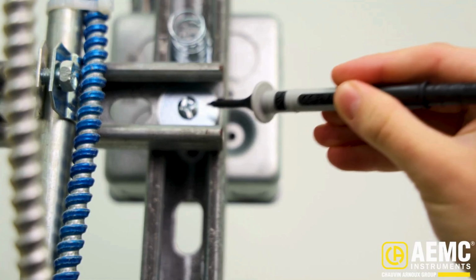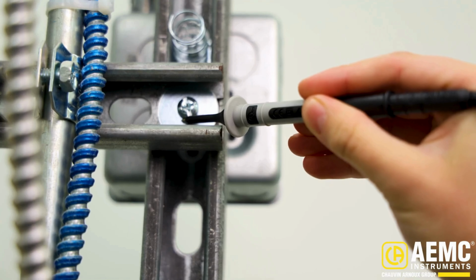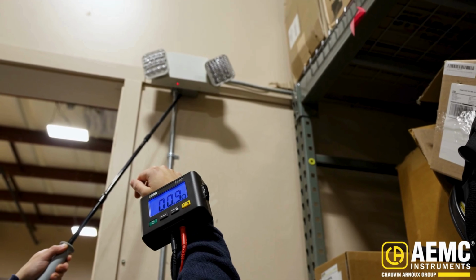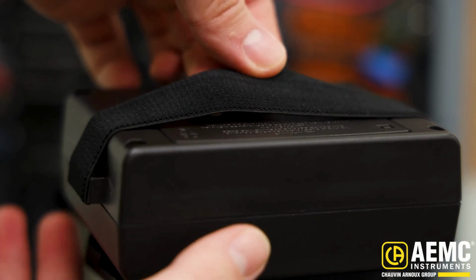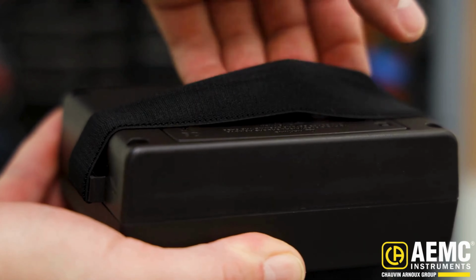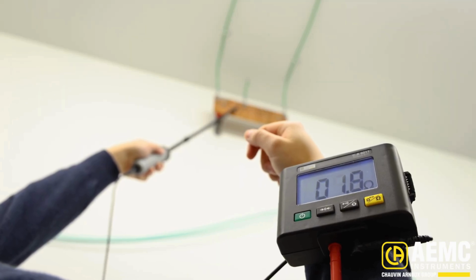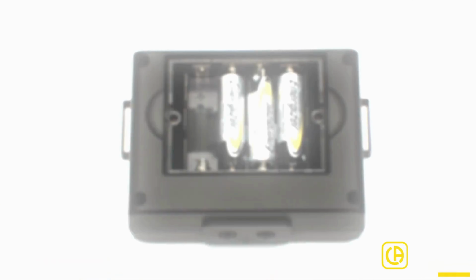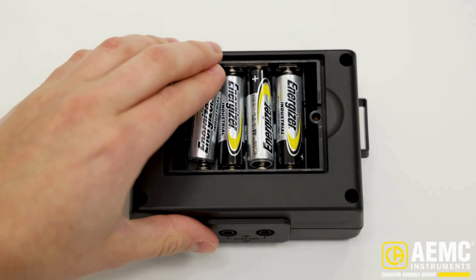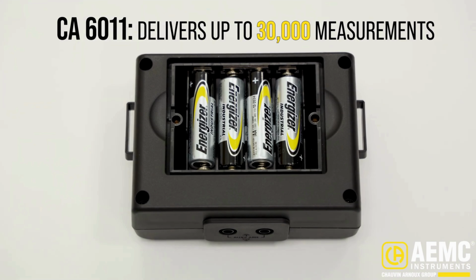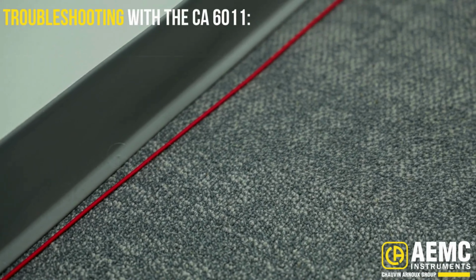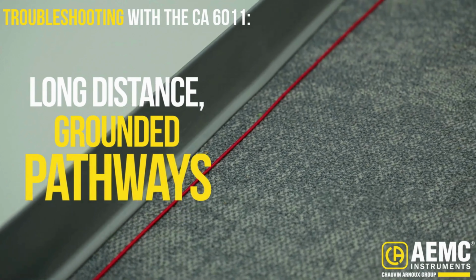Once it's on and in test mode, you don't have to push a test button for every measurement. Just touch the probe to each point, and the instrument automatically drives current and updates the reading. That keeps your workflow fast and hands-free. The model CA6011 is built for daily field use. It comes with a comfortable elastic wrist strap and durable housing designed to handle real job site conditions. Powered by 4 standard AA batteries, the instrument can deliver up to 30,000 measurements in typical operation. It's ideal for troubleshooting long-distance grounded pathways, as well as commissioning or large inspections.